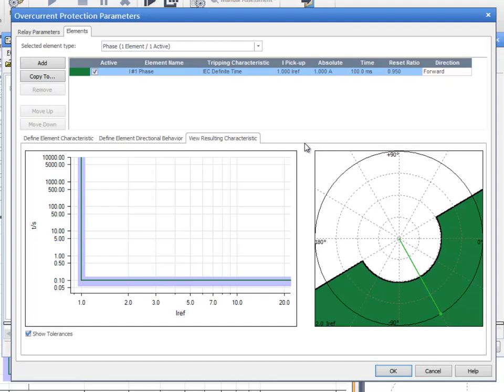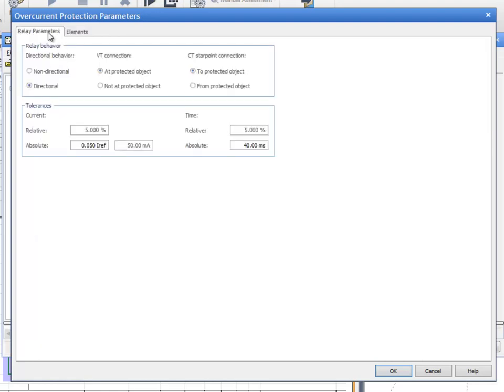To keep all these concepts in mind, we will proceed by configuring the overcurrent block according to the relay we are testing in the OCC file, that is, a non-directional relay with two definite time elements.